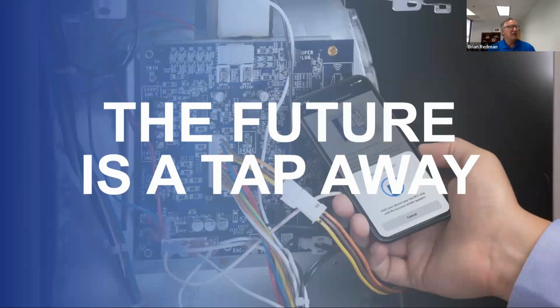Earlier you said the unit needed to be off to connect. If we're running the self-test, when in the sequence do we turn the power back on? The app will guide you through all of that. You'll do the connection and a screen will pop up saying upon power up, it will start the cycle and sequence. So after that connection and prompt, you can tape your door switch and/or put the door back on all the way from a complete safety perspective, and it will initiate that sequence on its own.